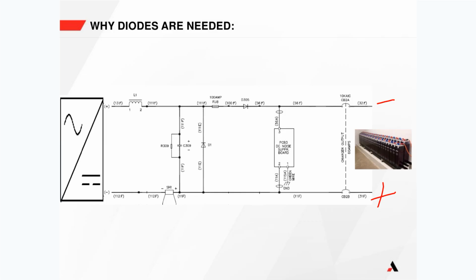Now if you do that and then close this breaker, you would put reverse polarity on this capacitor, which is very bad, and reverse polarity on the charger, which is very bad - you could cause damage. But look, we have this diode here, and it will allow current to flow that way.